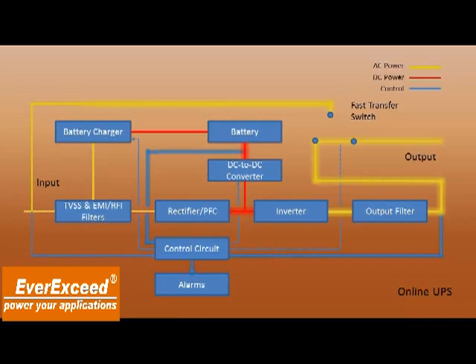We lose power. You see that there's not a whole lot of change. Nothing really transfers. We have an alarm for the loss of power. Basically, the battery is providing DC that goes to the inverter instead of the rectifier. So no transfer. It adds no break whatsoever in the output voltage.